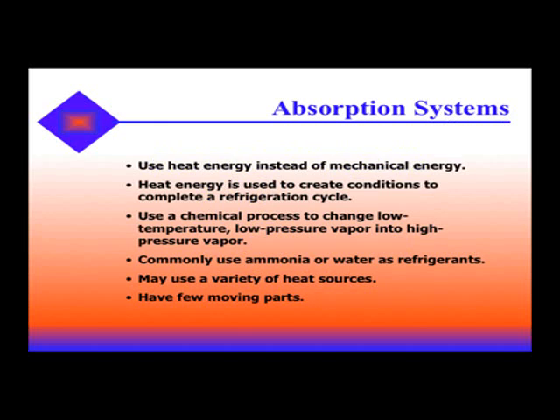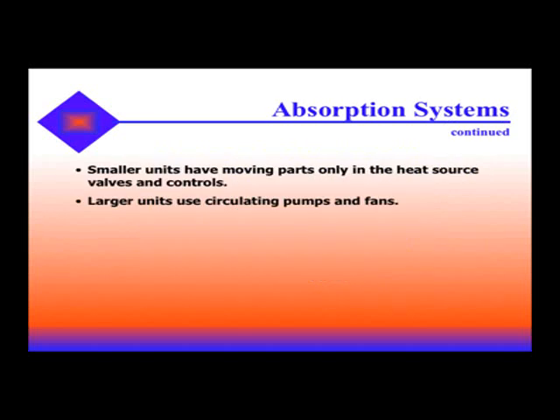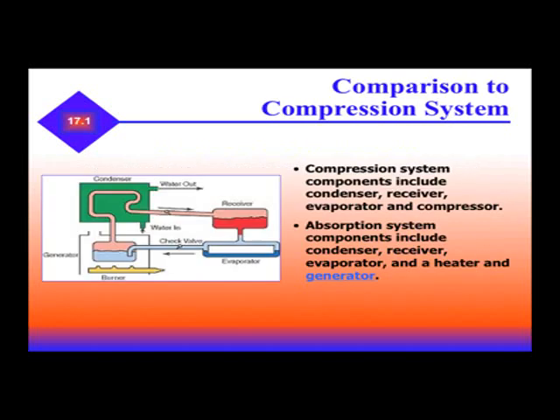Absorption systems commonly use ammonia and water as refrigerants. They may use a variety of heat sources, and they have very few moving parts. Smaller units have moving parts only in the heat source — for example, the valves and controls on a gas valve. Large units sometimes use circulating pumps and fans as well.